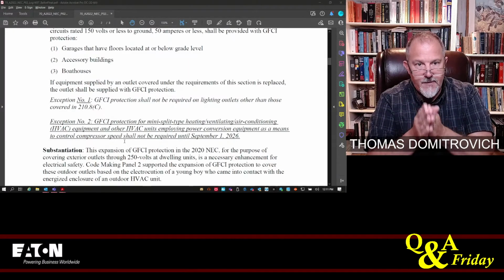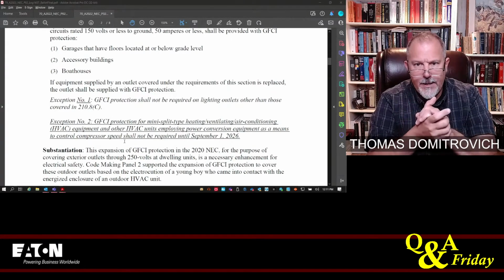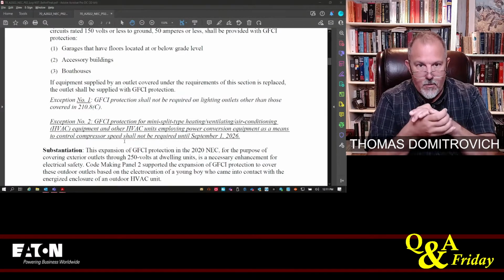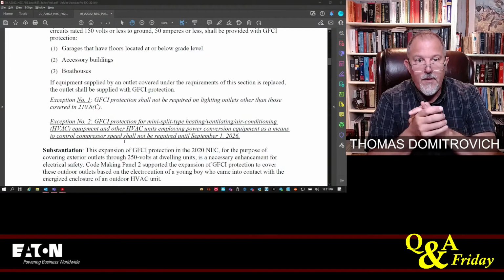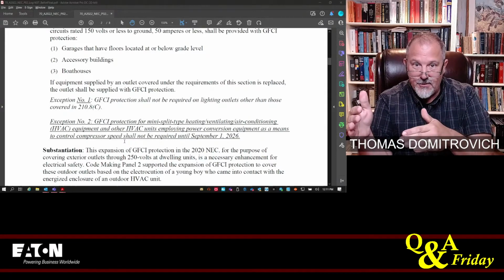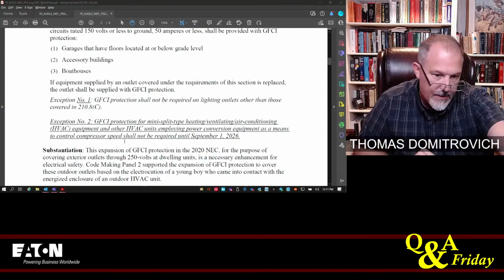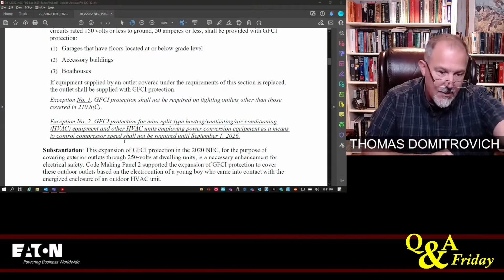Exception number 2, GFCI protection for mini split type HVAC air conditioning equipment and other, and it has an expiration date, September 1st, 2026. So we got a stay of execution, so to speak, for this equipment. Now that was the technical committee. The technical committee passed that one, didn't pass the other, which was if it was a listed HVAC equipment, that didn't pass at the technical committee.